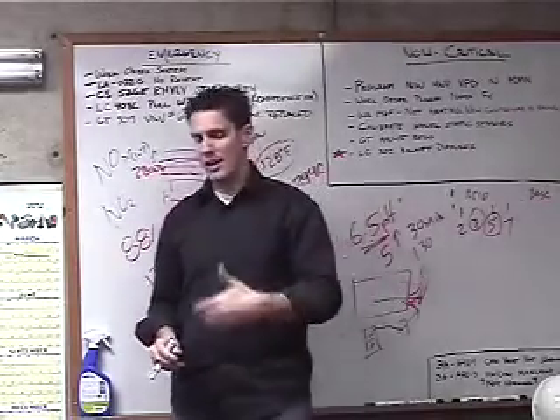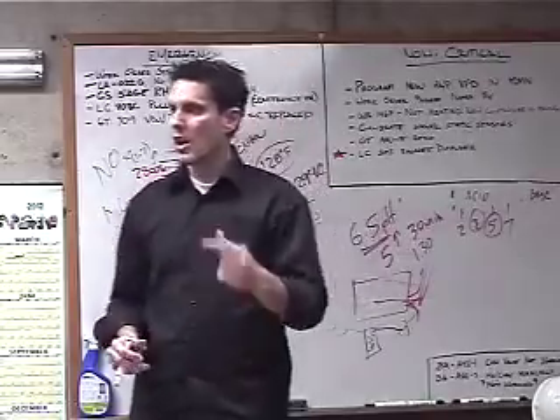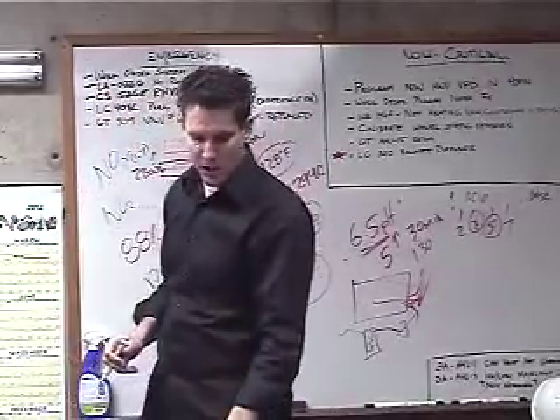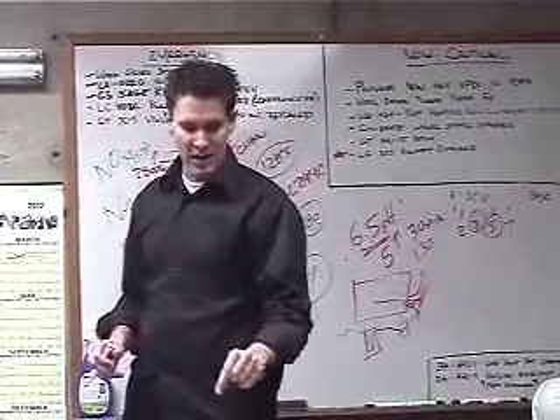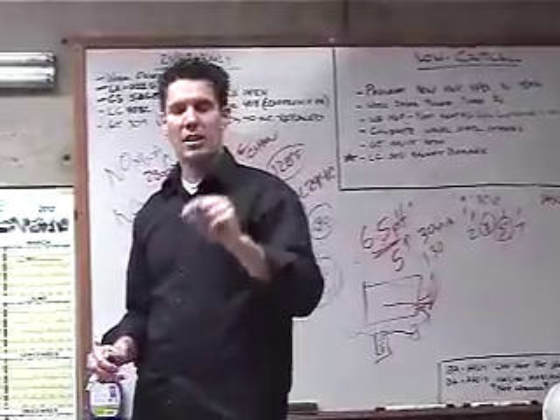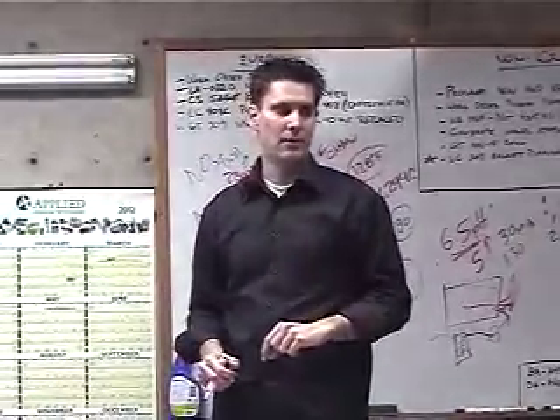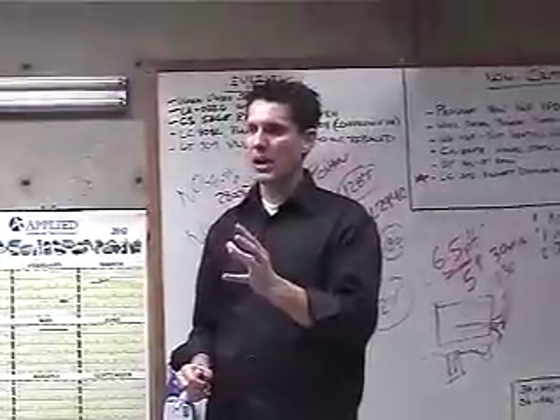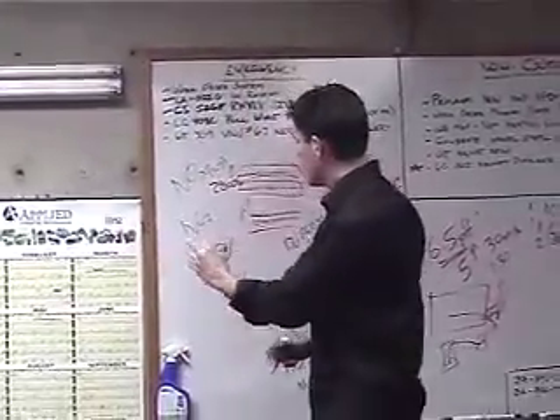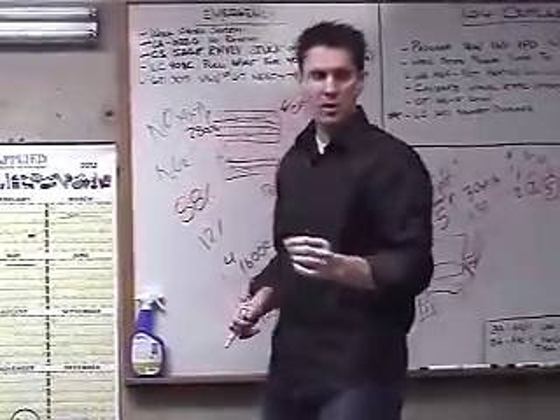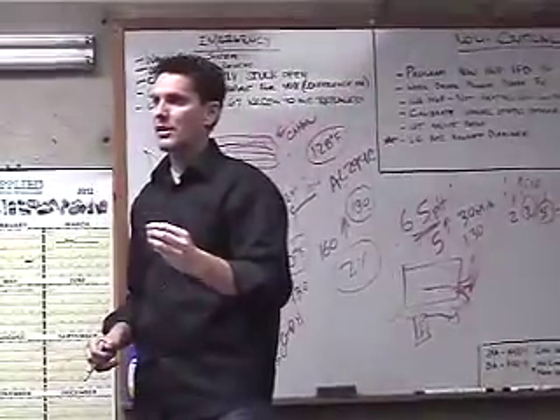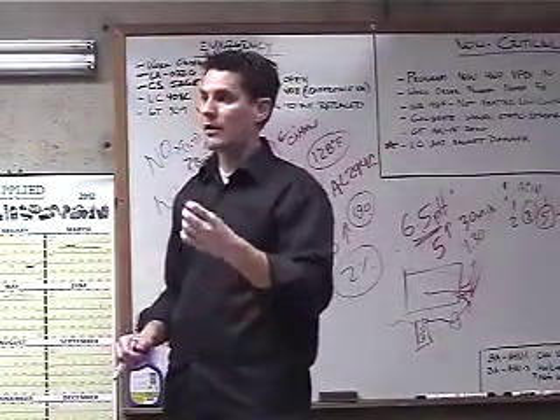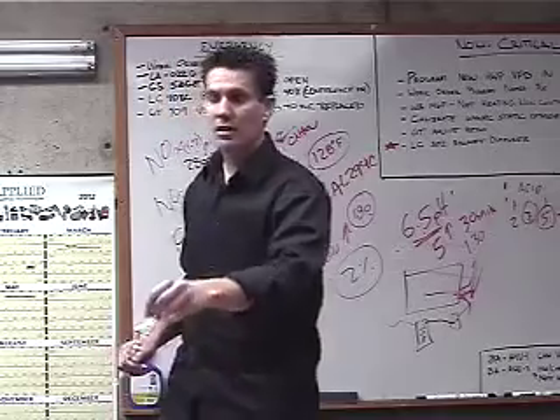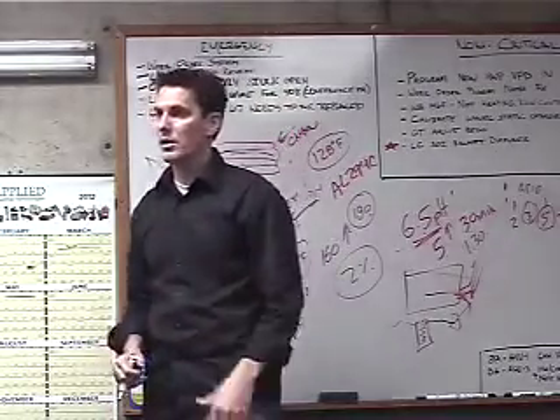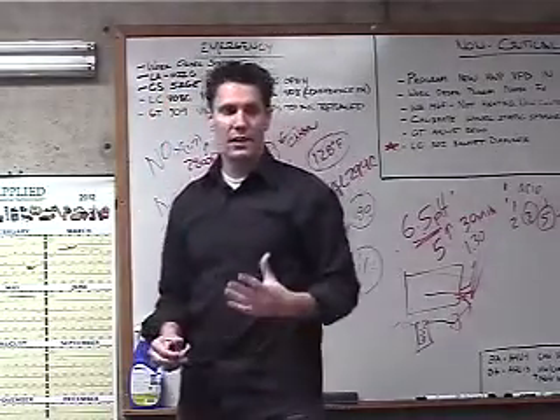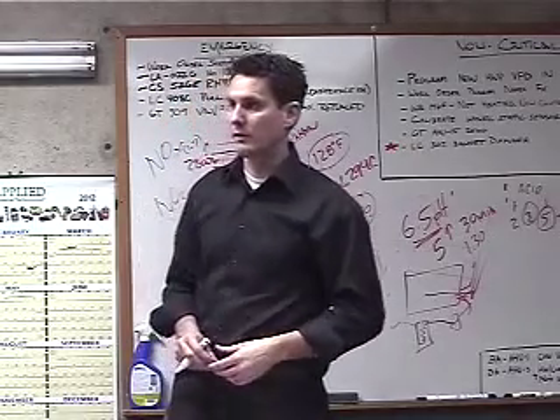So these are things, again, simple little things that will change. That's why it's going to become extremely important when we go over the maintenance requirements. You're going to notice in there, it keeps saying, check for blockage in the flue. Because any air restriction, anything that's going to restrict the amount of air that's coming into here is going to change your combustion rate. If it's blocked, you're going to start running rich. You're not going to have enough oxygen, just like that candle. You're going to start to build up soot. You're going to crud up your boiler. You're going to put a whole lot of pollutants out. It's not good. It's going to kill your boiler really fast.